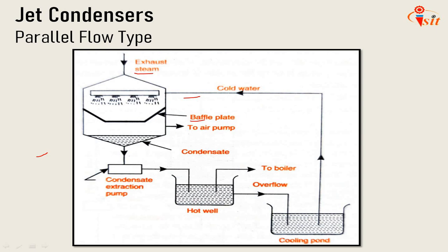An extraction pump at the bottom discharges the condensate to the hot well, from where it may be fed to the boiler if the cooling water being used is free from impurities. A separate dry pump may be incorporated to maintain proper vacuum.